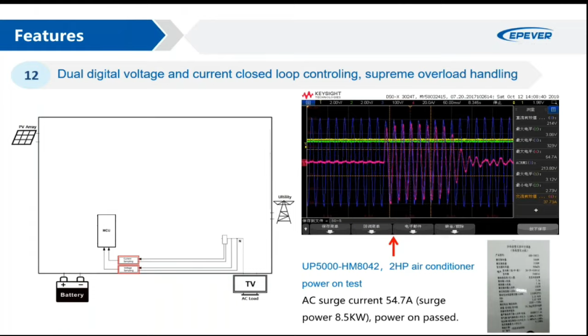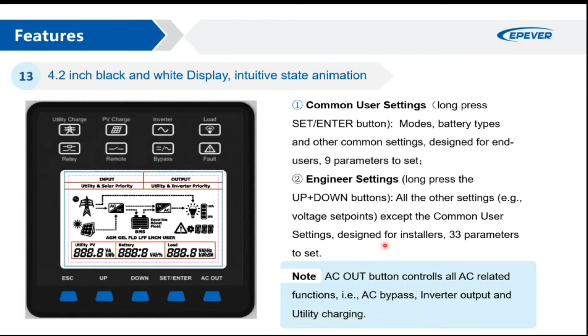So you can set the parameters of your system. This could be done with the LCD. We have two sets of parameters, the common user settings and the engineer settings. You can set the common ones by long pressing the set button, and the engineer settings by long pressing the up and down buttons. It could be anything, like the LVD, voltage disconnection and voltage reconnection criteria. You can just set these parameters using the LCD itself.